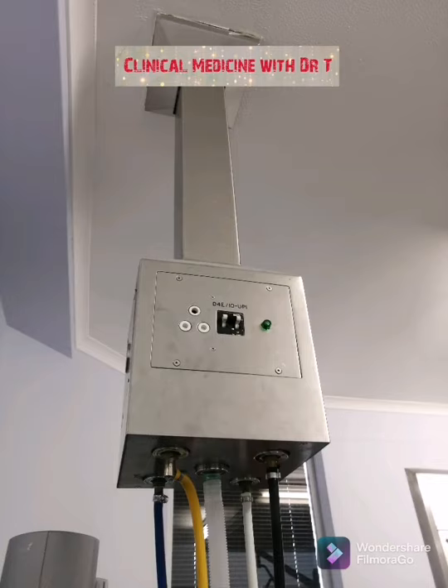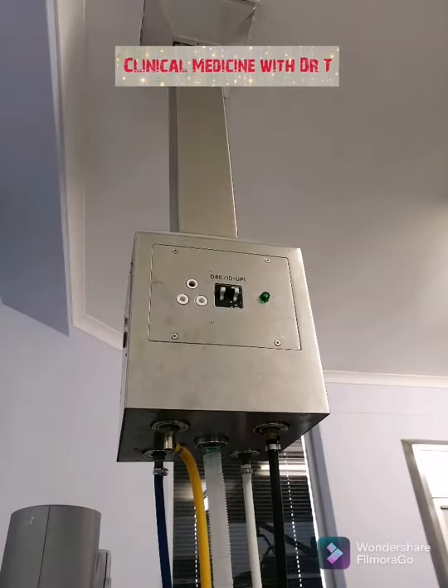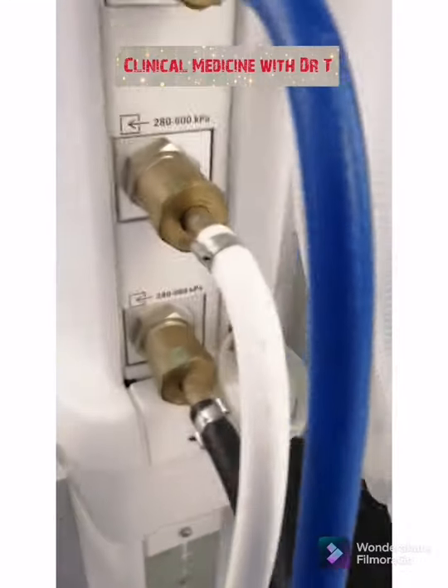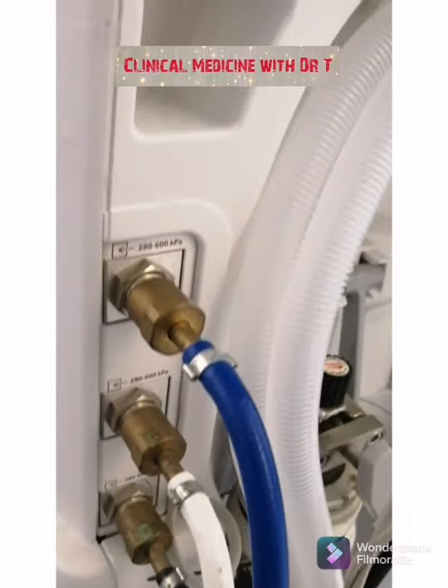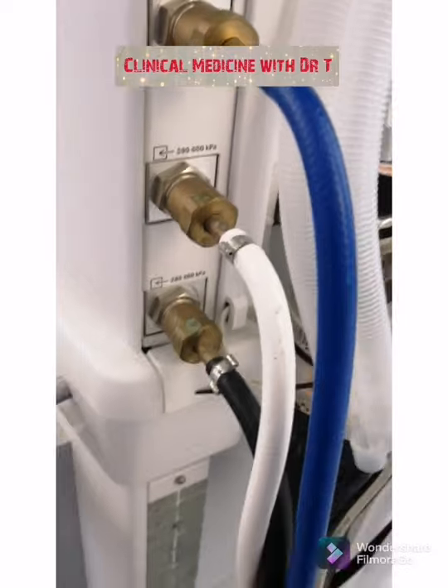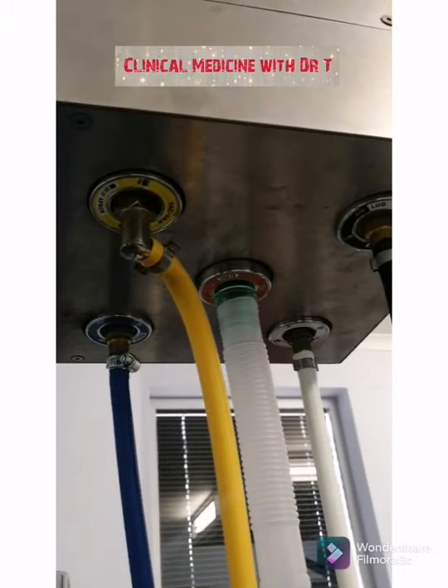It's mounted against the roof, and that's where we connect our gases to the machine. The gases come from the central supply and get into theater. When they get into theater, we use those pipes to take the gases into the machine. So the patient receives the gases from the machine, or via the machine.